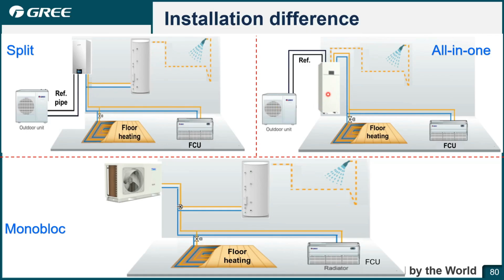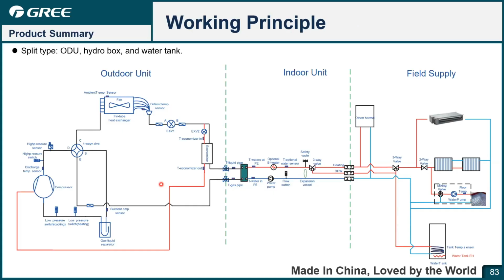However, for the all-in-one, the indoor unit is more compact. Even you can install in the room, and the space occupation is smaller. However, for the monoblock, no need to connect the copper pipe, so maybe the installation is a little bit easier. Yeah. Okay, that's the installation difference for the 3 types.